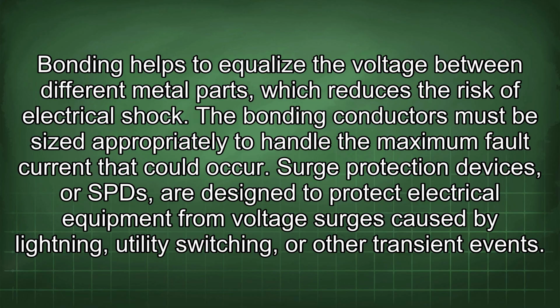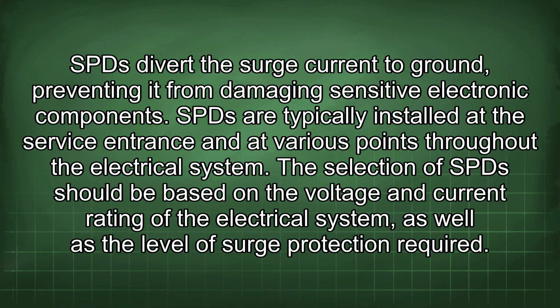Surge protection devices, or SPDs, are designed to protect electrical equipment from voltage surges caused by lightning, utility switching, or other transient events. SPDs divert the surge current to ground, preventing it from damaging sensitive electronic components. SPDs are typically installed at the service entrance and at various points throughout the electrical system. The selection of SPDs should be based on the voltage and current rating of the electrical system, as well as the level of surge protection required.